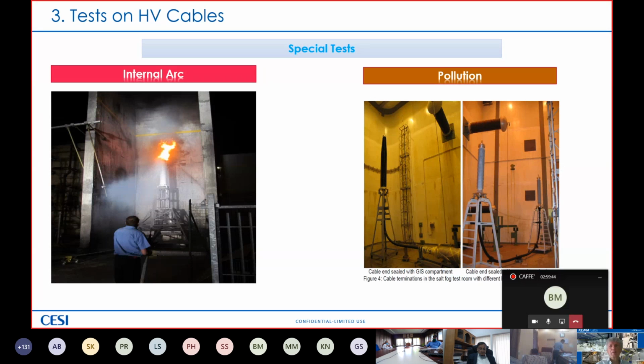Second reason, it's a practical reason, because in order to deliver this test that normally is performed from 30 kiloamps up to 80 kiloamps up to 3 seconds, in order to deliver such a power, Terna, that is the Italian utility, allowed us to have this connection only during nighttime in order to avoid any kind of blackout in the Milano area. That's the real reason.